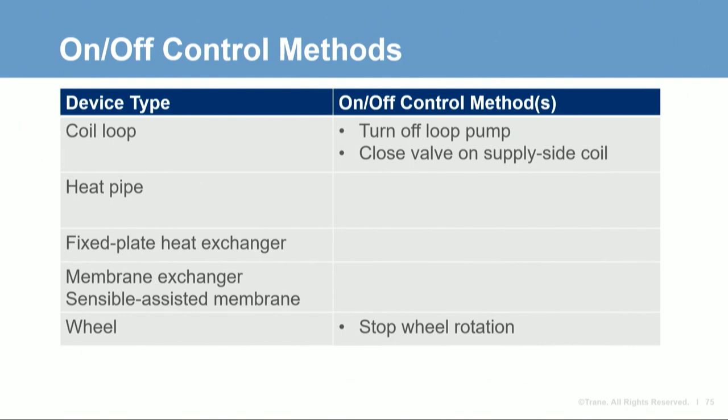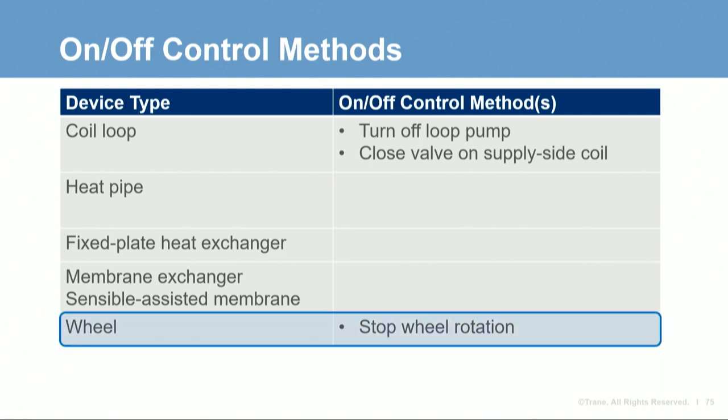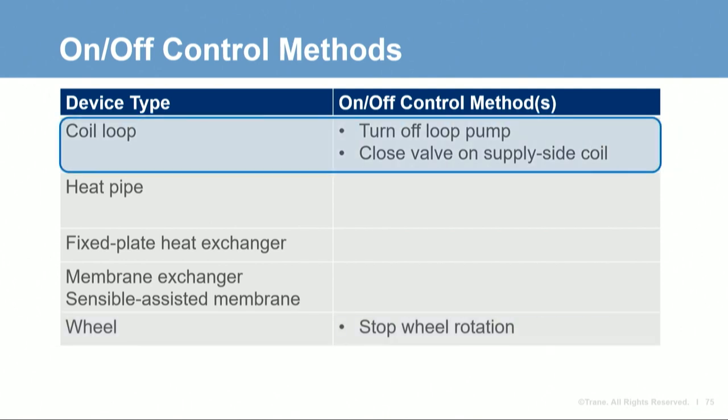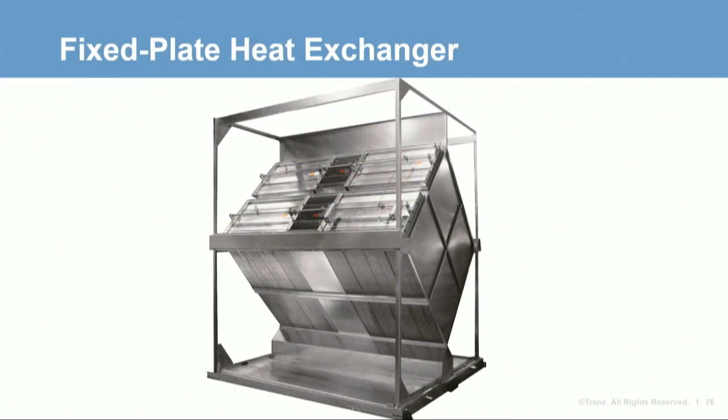The approach for turning off an energy recovery device differs among the various technologies. For a wheel, just turn off the motor to stop rotation. For a coil loop, turn off the circulating pump, or in the case of a networked coil loop, close the valve for that specific supply side coil. For a fixed plate or membrane heat exchanger, you need face and bypass dampers to prevent one of the two airstreams from passing through the device.